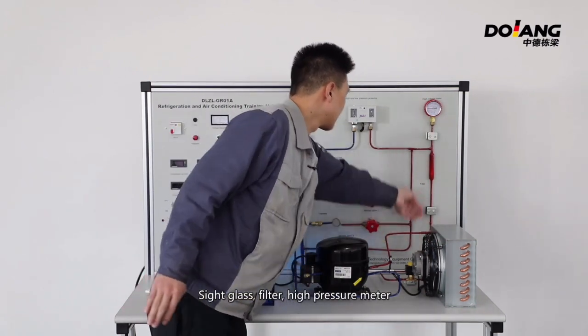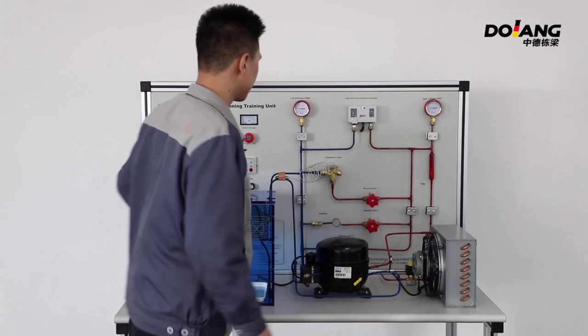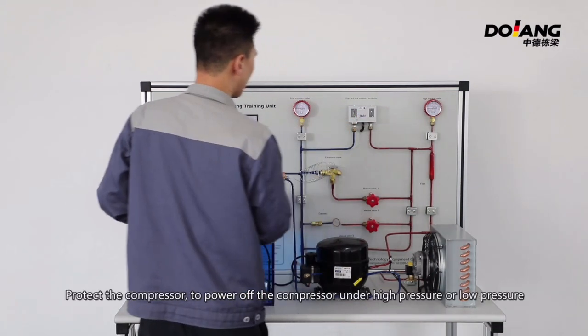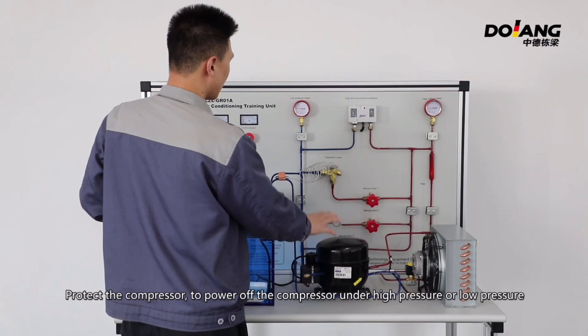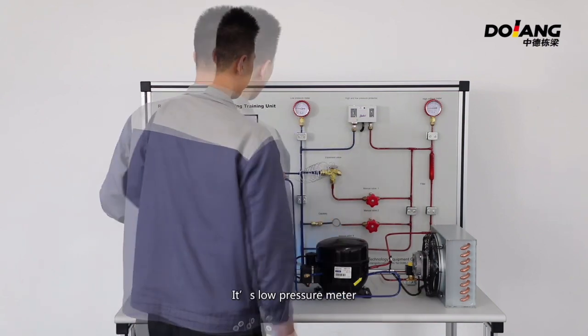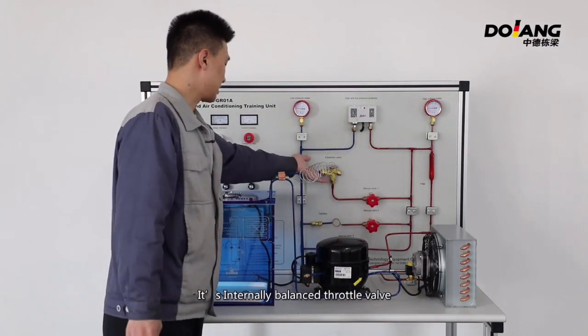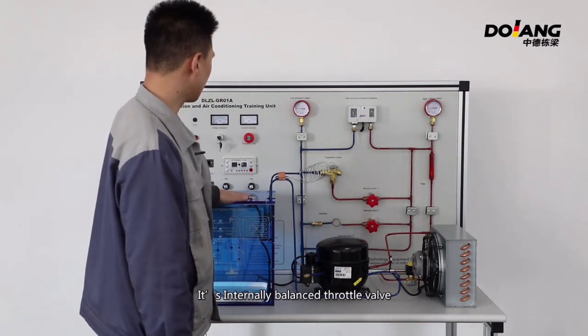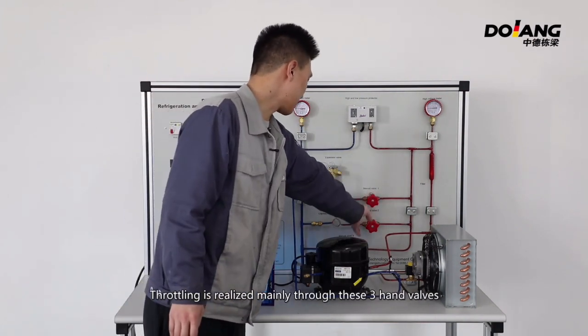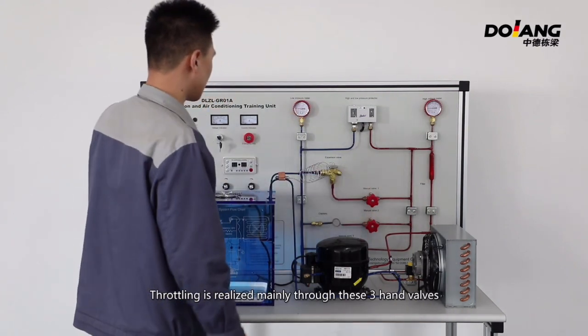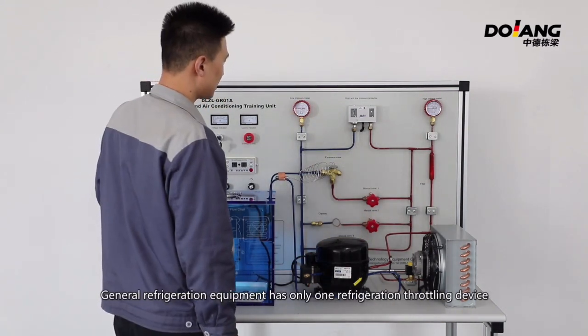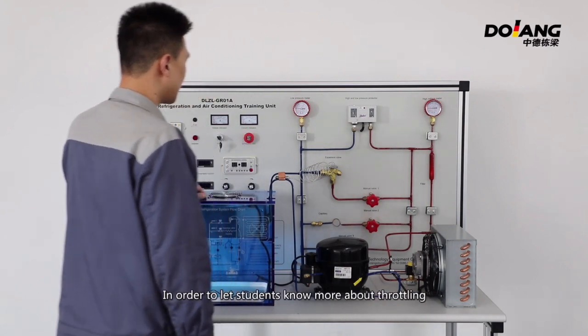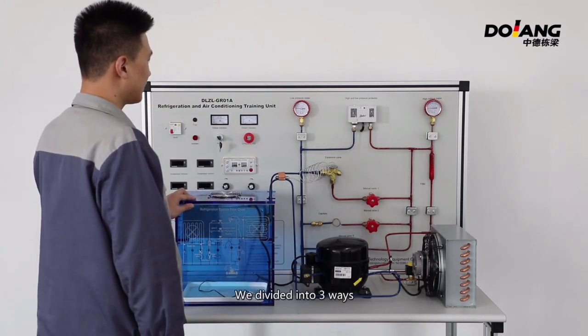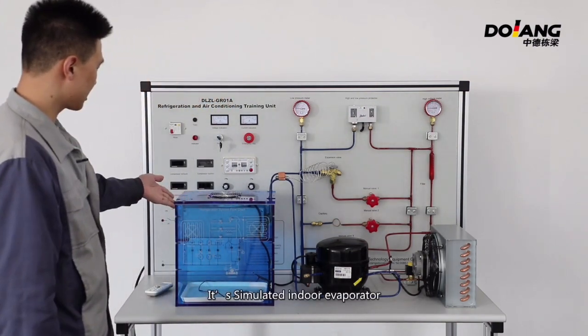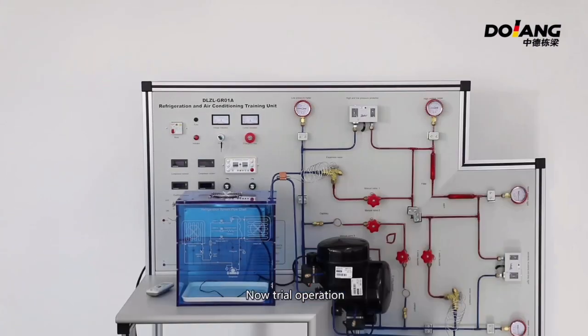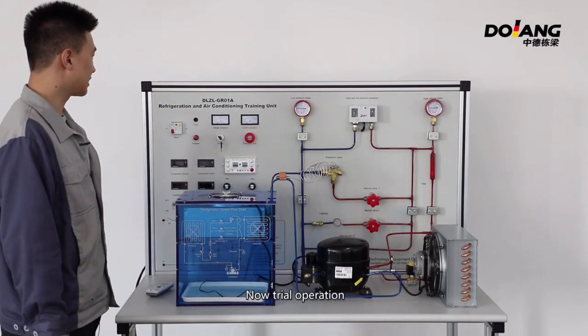Sight glass, filter, high pressure meter, high and low pressure protector. Its function is to protect the compressor, to power off the compressor under high pressure or low pressure. It's a low pressure meter. It's an internally balanced throttle valve. Throttling is realized manually through these 3 hand valves. General refrigeration equipment has only one refrigeration throttling device, in order to let students know more about the throttling. We divide it into 3 ways. It's a simulated indoor evaporator. Now, trial operation.